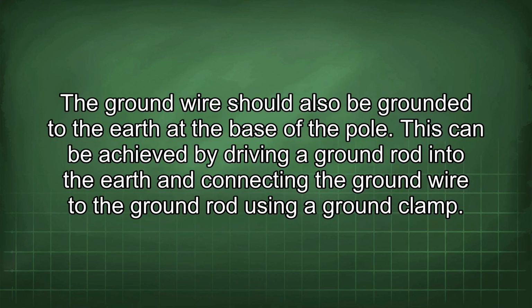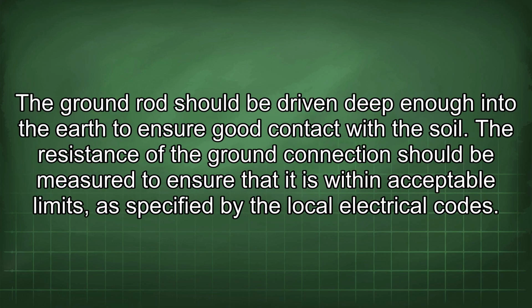The ground wire should also be grounded to the earth at the base of the pole. This can be achieved by driving a ground rod into the earth and connecting the ground wire to the ground rod using a ground clamp. The ground rod should be driven deep enough into the earth to ensure good contact with the soil. The resistance of the ground connection should be measured to ensure that it is within acceptable limits, as specified by the local electrical codes.